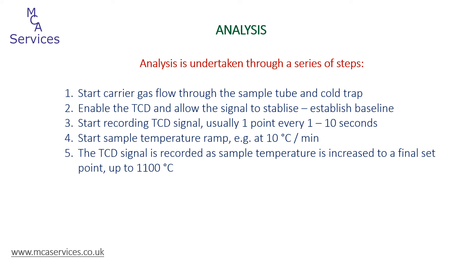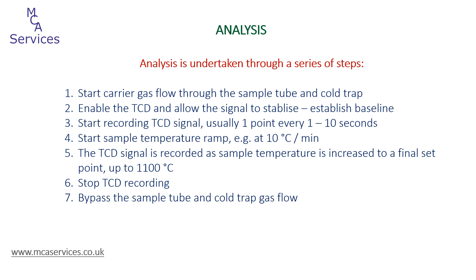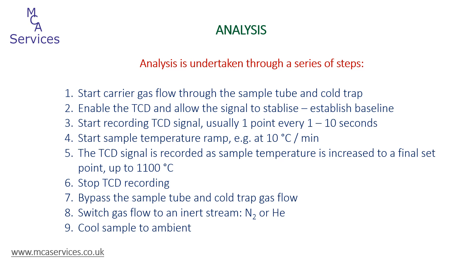The TCD signal is then recorded as the sample temperature is increased to a final set point, which could be as high as 1100 degrees on the AutoChem, but the actual endpoint will depend on the anticipated profile from the sample. There's not a lot of point in continuing once any reaction has been completed — for example, copper oxide reduces at quite a low temperature, so there's no point in going beyond around about 300 to 350 degrees. Once the endpoint is reached, we stop recording the TCD signal. We then bypass the sample tube and the cold trap, switch the stream to an inert gas such as nitrogen or helium to protect the TCD, and cool the sample from the furnace to around about ambient temperature.